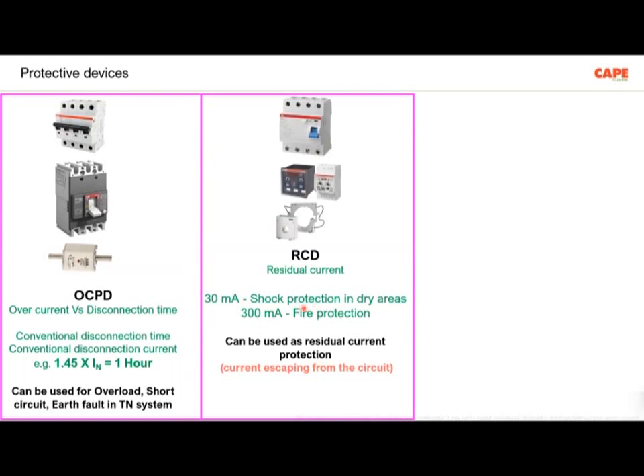That means if you want protection from electric shock, you must use an RCCB of 30 milliampere or less. 300 milliampere is calculated as the requirement. Less than 300 milliampere is for fire protection. So there are two things: 30 milliampere shock protection and 300 milliampere fire protection. Of course, we must understand that the 300 milliampere fire protection is based on a 230 volt line. If the operating voltage is a little bit higher, there is still a debate going on.